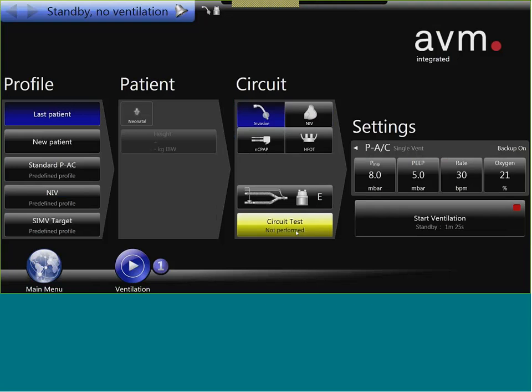Thank you, Christian. And can you now please tell us, this is for Sayi again, the particle size of the aerosol during nebulization? That's not up to the bellavista. So bellavista is just delivering 8 liters of additional flow for the nebulizer. So if you want to know the particle size, you have to go for the instructions of the nebulizers you want to use. And does the BV series employ inspiratory valve? Yes, it does. Okay, thank you very much.